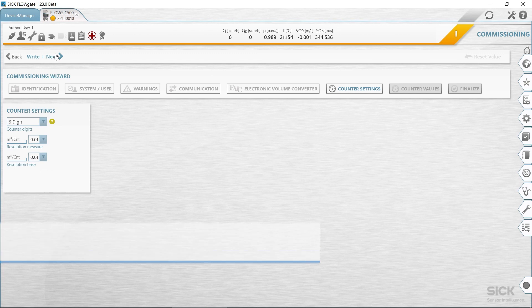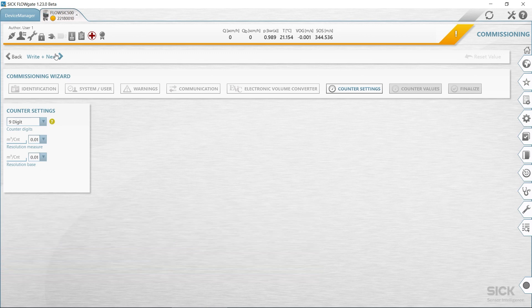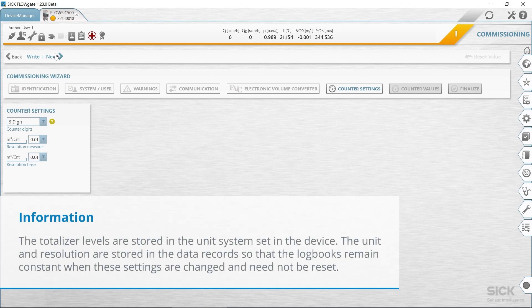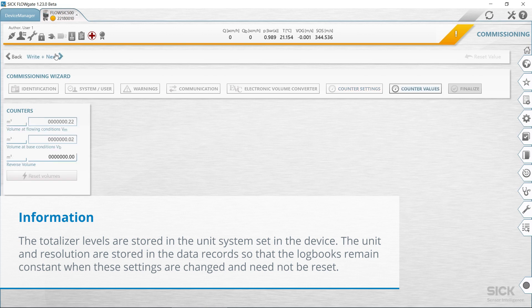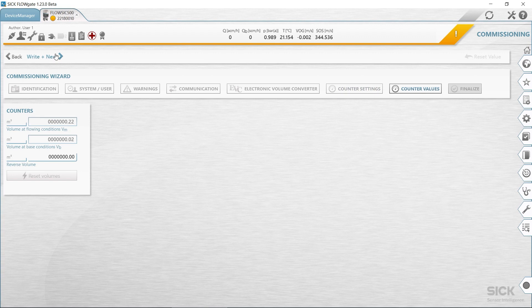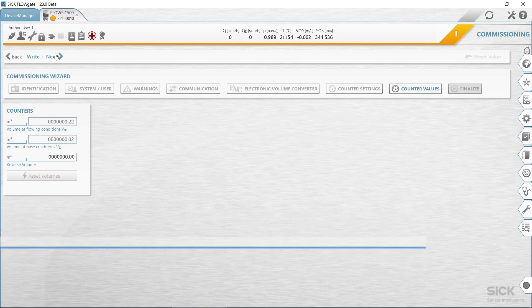At the meter settings, configure the significant digits for the meters. Determine the resolution for the meters. The totalizer resolution can be set in the range from 0.001 to 100 in increments to factor 10 for the volume at flowing conditions and the volume at base conditions. It is therefore necessary to multiply the totalizer level with the corresponding totalizer resolution to interpret the totalizer level.